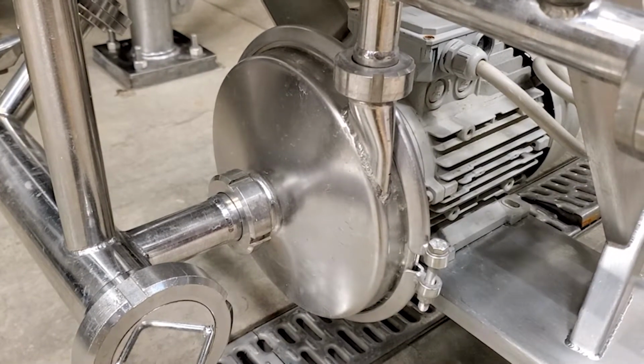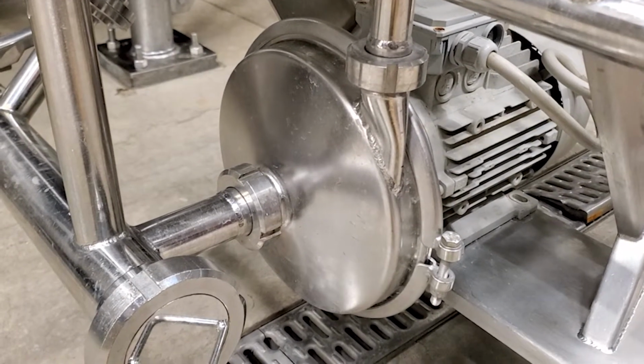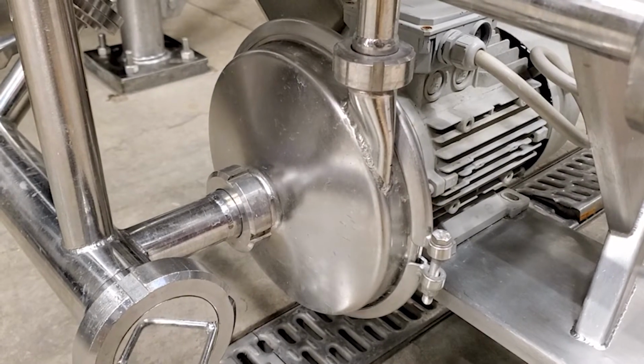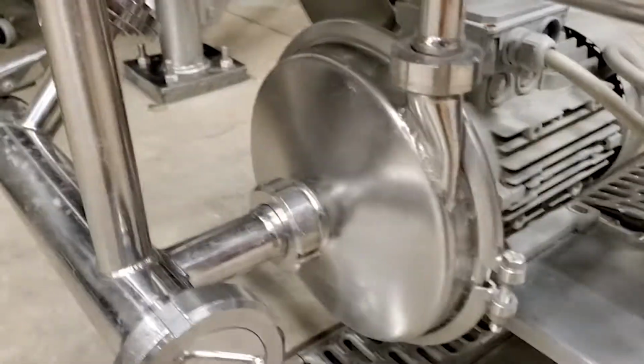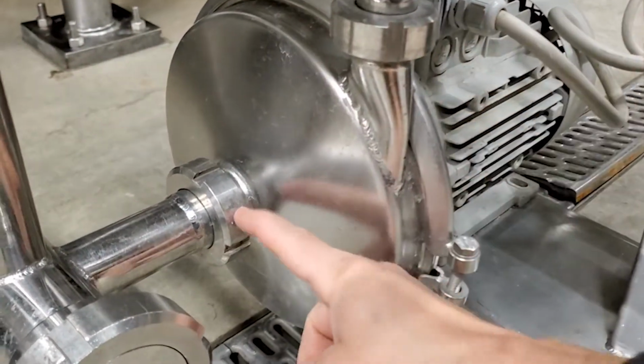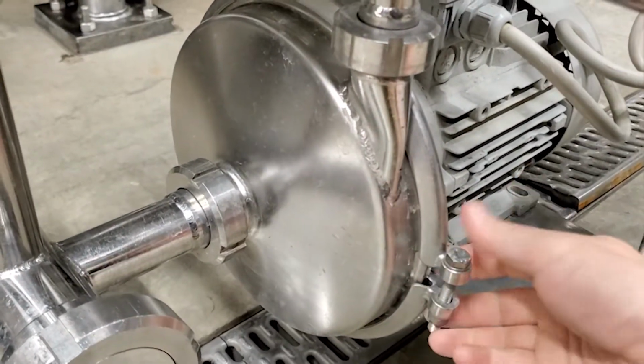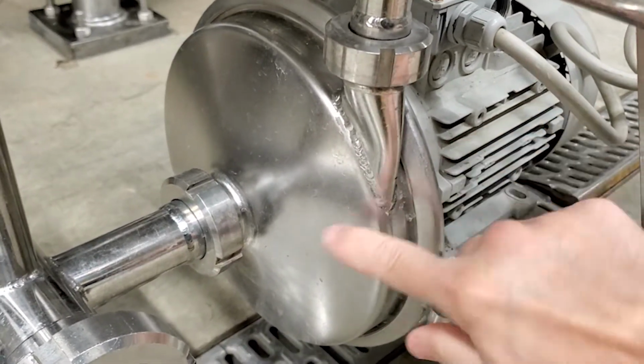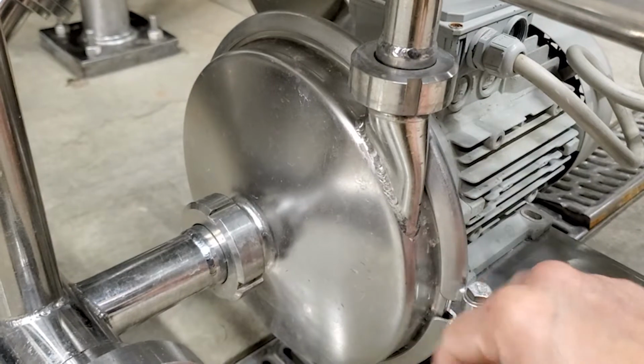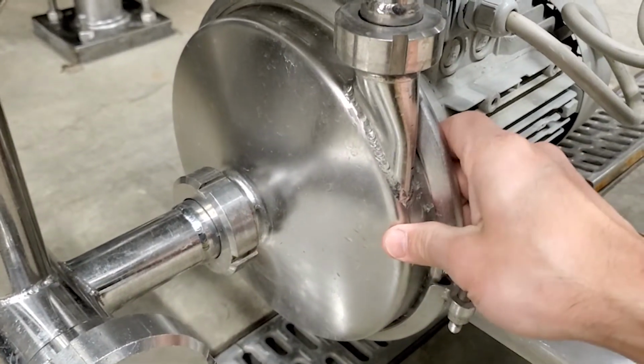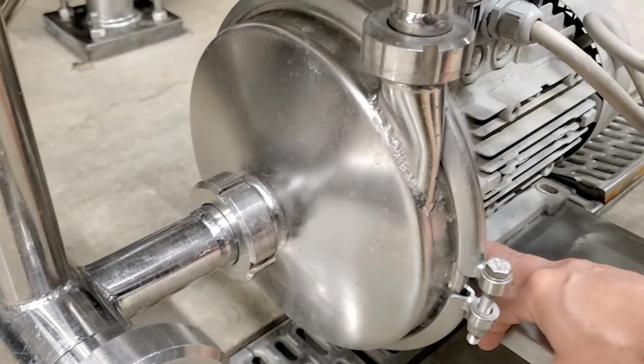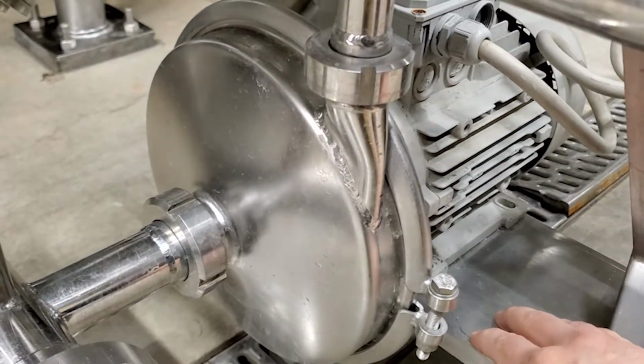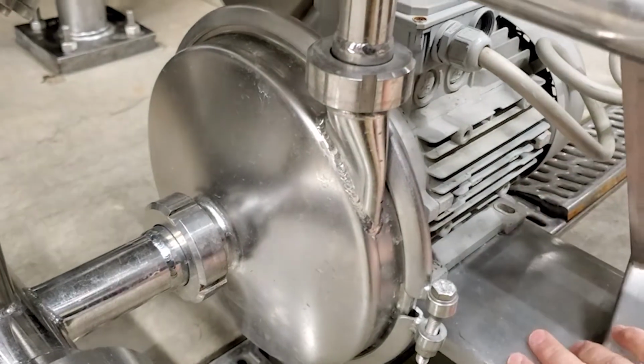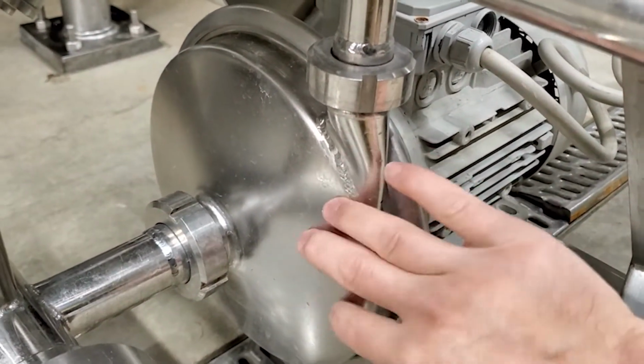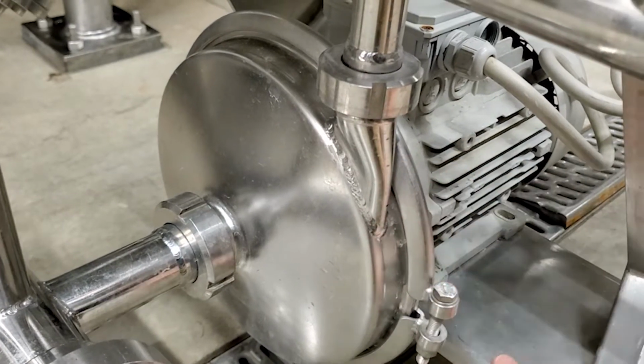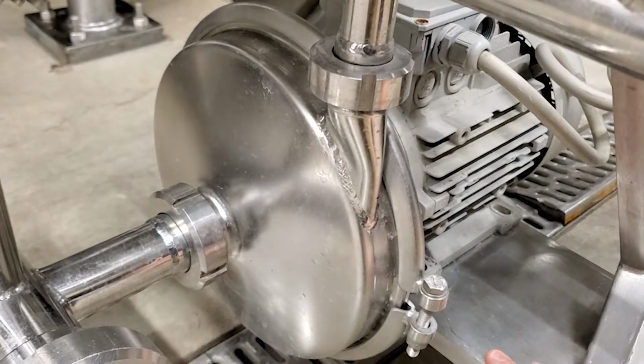I'm just about to take this pump head apart so we can replace the seal inside the centrifugal pump here. There are a couple DIN fittings, one here and one there, so we're going to take both of those off. We're also going to take off this retention ring that holds the back plate and front plate together. Once we take off the DIN fittings and the retention ring, we're going to take out the bolts that hold the motor to the frame and slide that whole motor back. Then we should be able to remove the front plate from the back plate, which will allow us access to the O-ring and the seal.